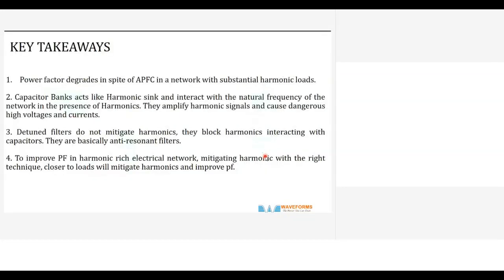The important thing about this is that the power factor degrades in spite of the APFC network with substantial harmonic load. When there's high harmonic load, the automatic power factor correction does not really help at all. In fact it can worsen things because of resonance. Capacitor banks act like harmonic sinks and interact with the natural frequency of the network in the presence of harmonics. They amplify harmonic signals and cause dangerous high voltages and currents. If resonating at the fifth harmonic, and the fifth harmonic is normally, say, 10 amps, it can be 30 amps also. The voltages also can spike, and the capacitors can fail.